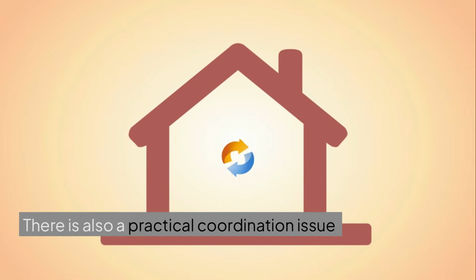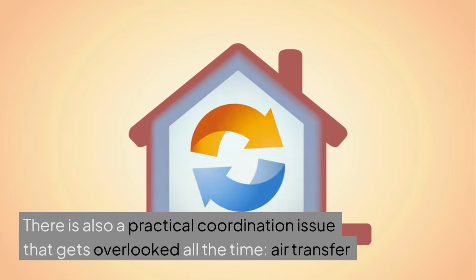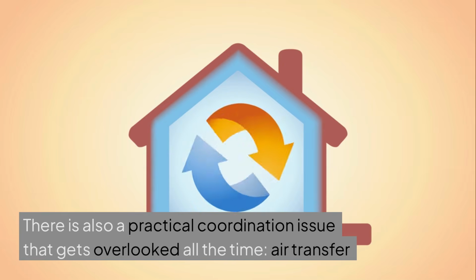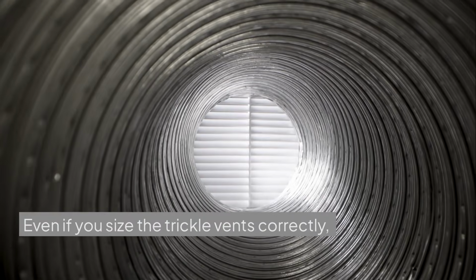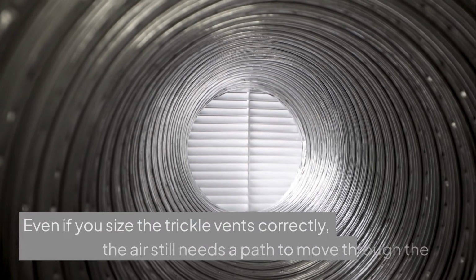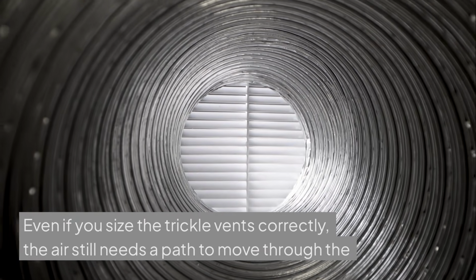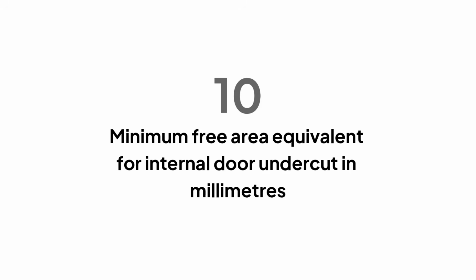There is also a practical coordination issue that gets overlooked all the time: air transfer through the dwelling. Even if you size the trickle vents correctly, the air still needs a path to move through the internal spaces. Paragraph 1.2.1 says internal doors should allow air to flow by providing a minimum free area equivalent to a 10 mm undercut in a 760 mm wide door.